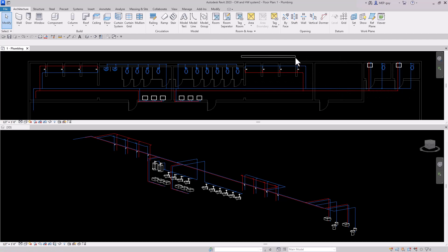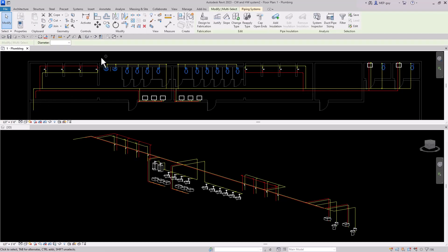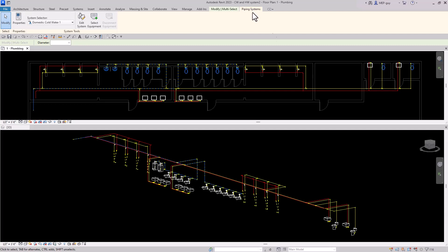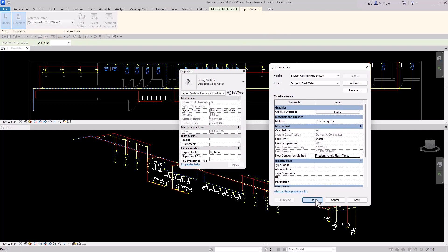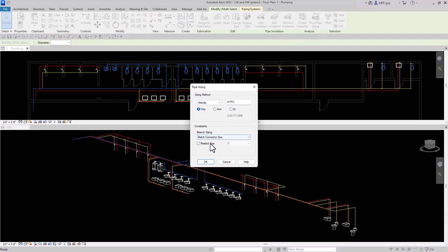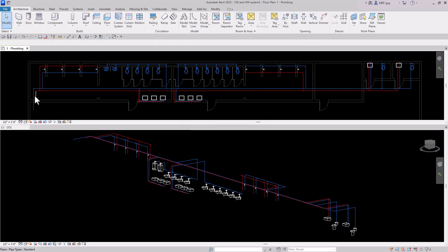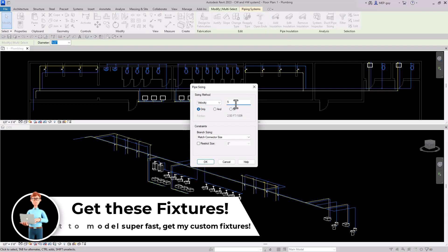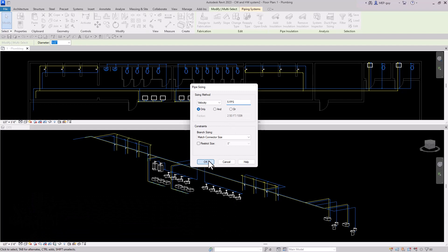The next thing we need to do is select all of the pipes that are not going to be sized per flush valve - so all the showers, the lavatories, and these tank fixtures over here. I'm going to select all the piping again and just deselect these water closets, because I don't need to size these again. I'll hold shift to deselect the mains as well. Now you can see only the showers, lavatories, and this network of piping to these flush tank type toilets are selected. We'd go to piping system, edit type, and this time we're going to change it to tanks, because that's how we want to size this. We'll use the duct pipe sizing tool, size it for 8 feet per second, and match the connector size. Now we're essentially done with the cold water. The hot water is a little easier - I can just tab into all these pieces, go to my duct pipe sizing tool again. Since it's hot water, we want to size it to maybe 4 or 5 feet per second depending on your standard, so I'm just going to use 5 for this. And then we've essentially sized that.